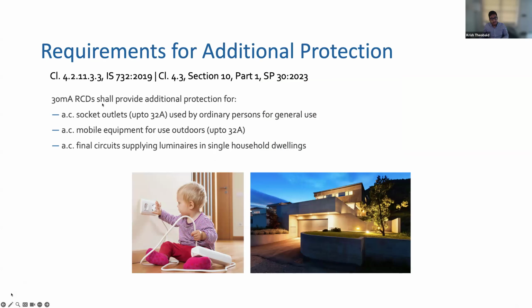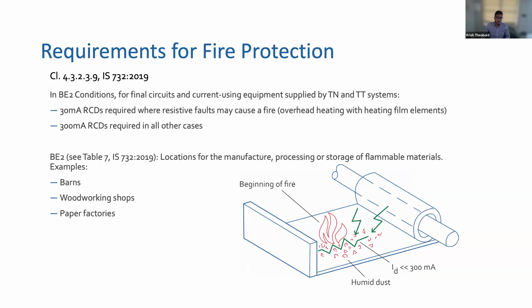This Indian standard says that a 30 milliampere RCD shall provide additional protection in 3 areas. Number 1, a socket outlet up to 32 amperes for use by an ordinary person for general use. That is any socket outlet in a home, office, factory, etc. up to 32 amperes has to be protected by a 30 milliampere RCD. Mobile equipment for use outdoors, like a lawn mower, is also required. And a final circuit supplying luminaires, any lighting circuits in domestic environments, also requires 30 milliampere RCDs. Any special location, for example, sauna, swimming pool, has separate requirements. But normal installations are socket outlets, mobile equipment, and AC final circuits supplying luminaires. A bathroom is also a special requirement where 30 milliampere is required.